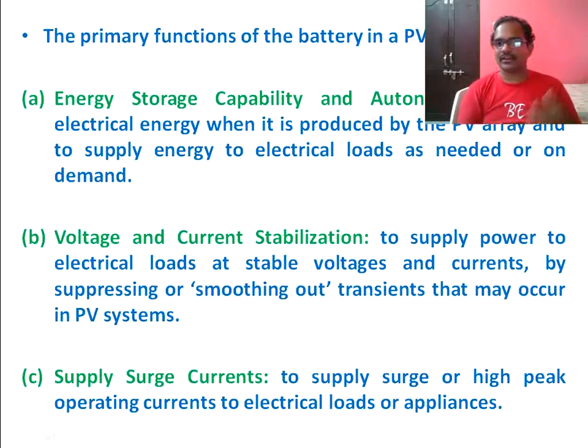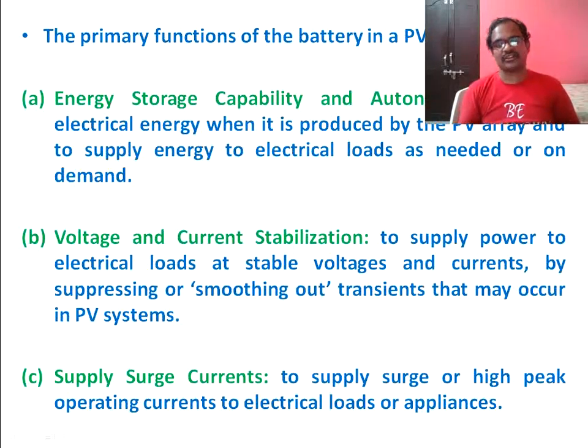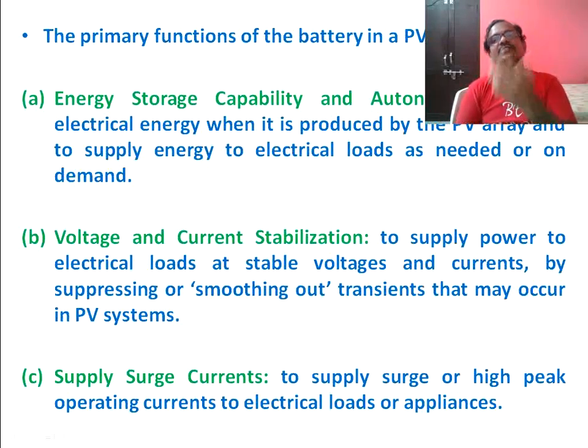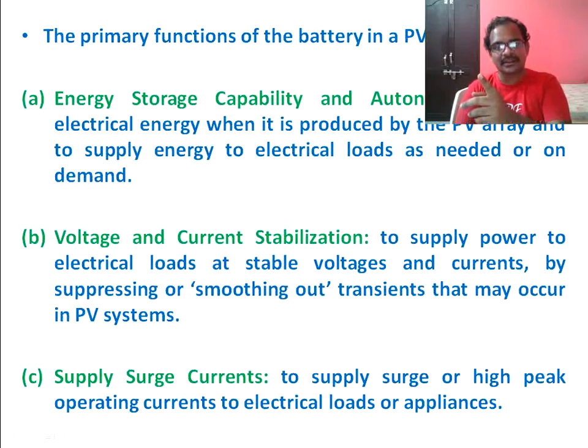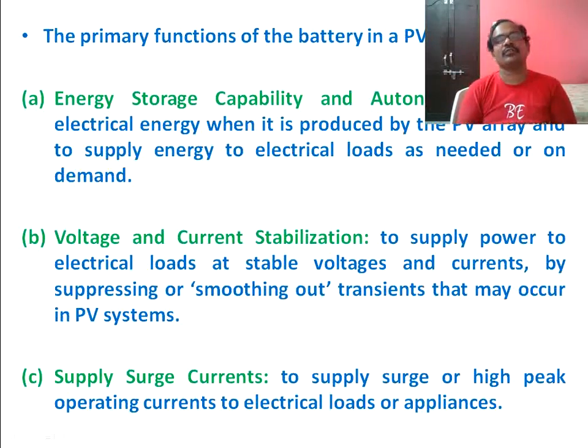Even though there is no solar radiation, your system should be capable of producing energy. If there is no sunlight, the panel stops working and the battery won't get charged. That is why you need to keep a number of days of autonomy. If you require 100 watt-hours per day, and you take two days of autonomy, you need to double the battery size, so the battery can last for two more days without sunlight.